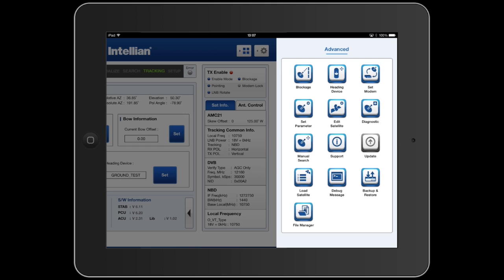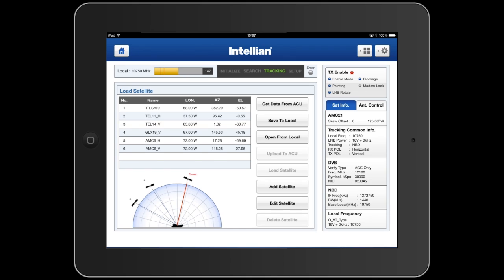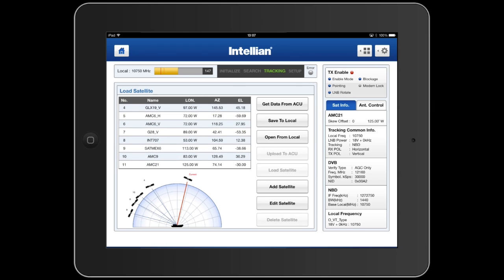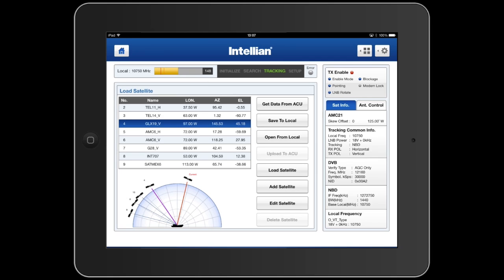Using the Load Satellite menu option, we can go into the system and load the satellite data from the ACU to the antenna, as well as interrogate the antenna to see which satellite it's watching. It is also possible using this menu to select a new satellite to point the antenna towards — simply scroll down the list, select the satellite we wish to use and hit the Load Satellite button. Selecting the new satellite allows the antenna to re-point and target the new satellite, as you can see on the pictogram and in the satellite information on the right-hand section of the screen.